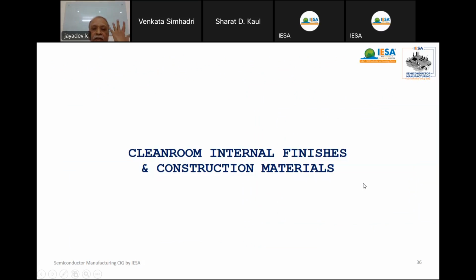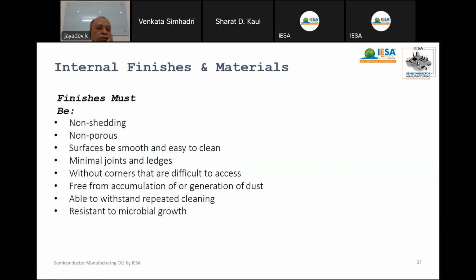Like internal finishes. Okay. Internal finishes, that is, whatever you encapsulate inside the room, should be non-shedding, non-porous, with smooth surfaces that are easy to clean, minimal joints and ledges, without corners that are difficult to access, free from accumulation and generation of dust, able to withstand repeated cleaning and resistant to microbial growth. These are important requirements of the wall, ceiling, the flooring, the wall panel.